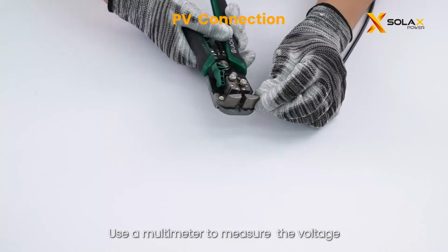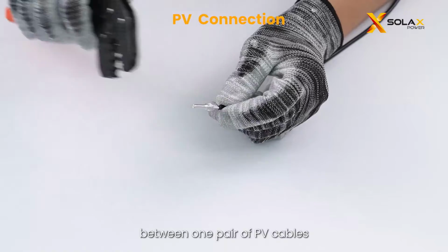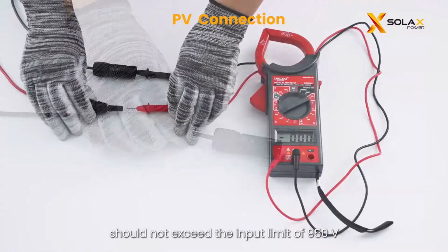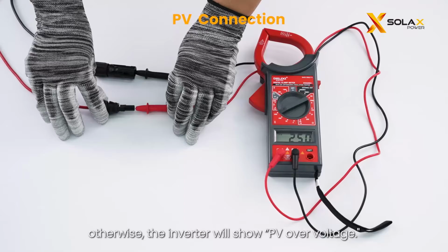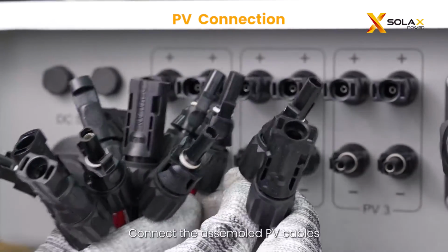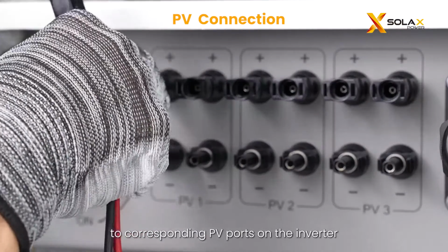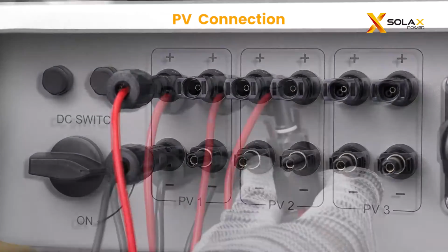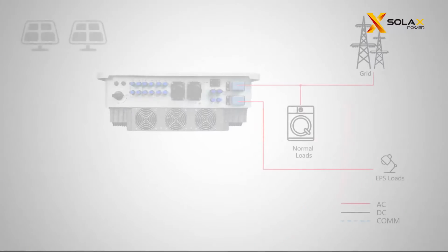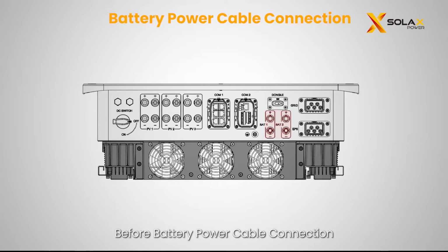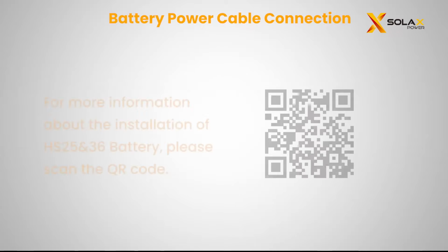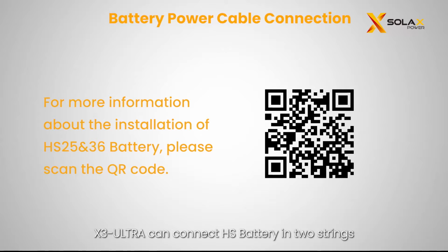Use a multimeter to measure the voltage between one pair of PV cables. The open circuit voltage should not exceed the input limit of 950 V, otherwise, the inverter will show PV overvoltage. Connect the assembled PV cables to corresponding PV ports on the inverter. Before battery power cable connection, please make sure the breaker of battery is in off position. X3-ULTRA can connect HS battery in 2 strings.